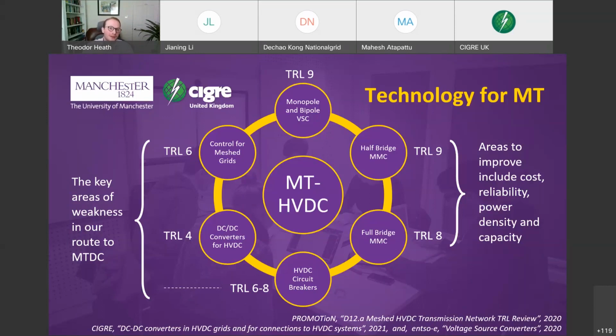We'll drop further down to TRL 6 for meshed grid control, multi-terminal grid control, which is in active research in both industry and academia. And we drop even lower to TRL 4 for DC to DC converters for HVDC, mainly due to the complexity and cost of these systems. The latter two, mesh grid control and DC to DC converters, are the key areas of weakness at the moment in this path to an HVDC supergrid, whatever form that may take, but not necessarily limiting us from achieving multi-terminal HVDC grids in general, as long as they've been planned around appropriate voltage levels.